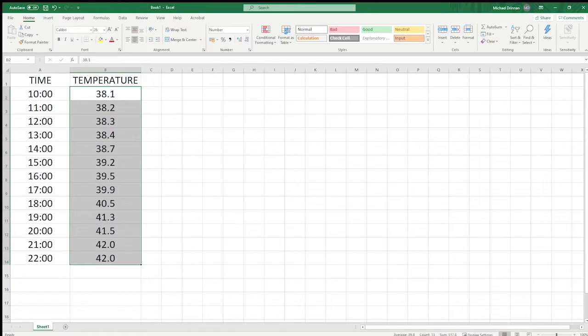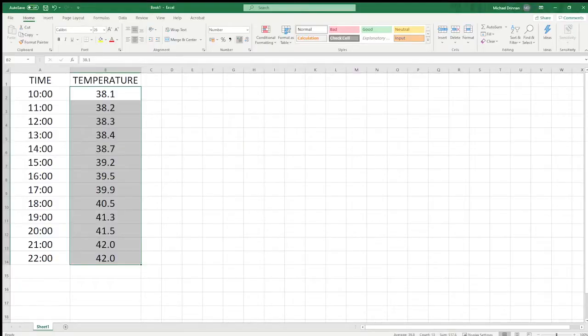You'll appreciate then that in order to set the sampling resolution for one of your physiological signals, you need to understand what you're going to use that measurement for. If you can understand the smallest change of your physiological signal that is of clinical importance, there's a rule of thumb called the rule of 10, which says something along the lines of your measurement resolution should be 10 times better than that. So for the sake of argument, if a 1 degree centigrade change in temperature is the smallest change that you would consider to be clinically significant, then your sampling resolution ought to be about 0.1 of a degree C.